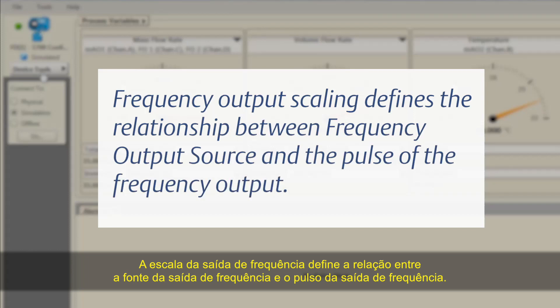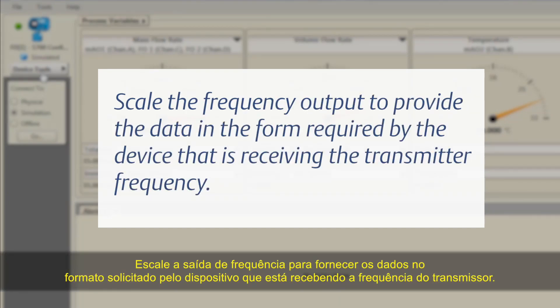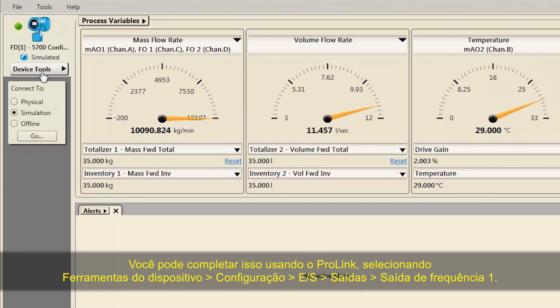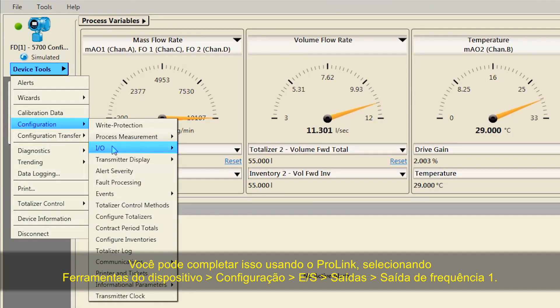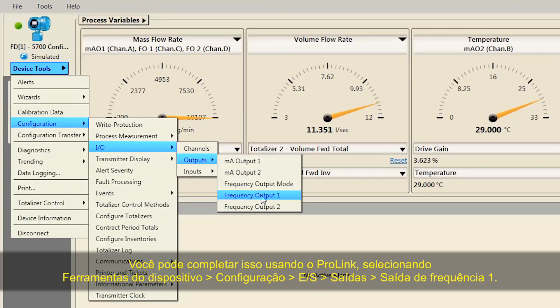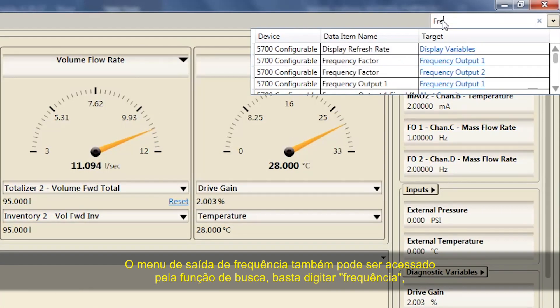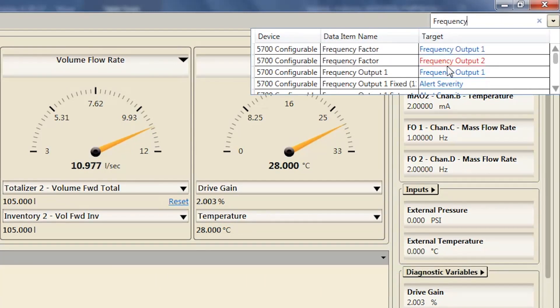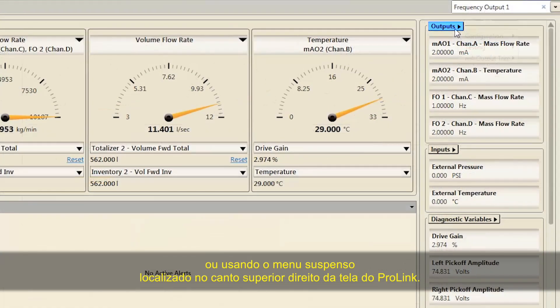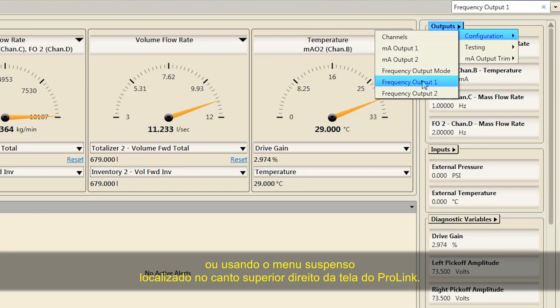Frequency Output Source specifies the process variable that is reported by the frequency output. Frequency Output Scaling defines the relationship between the frequency output source and the pulse of the frequency output. Scale the frequency output to provide the data in the form required by the device that is receiving the transmitter frequency. This can be completed using ProLink and selecting Device Tools, Configuration, I-O, Outputs, Frequency Output 1.